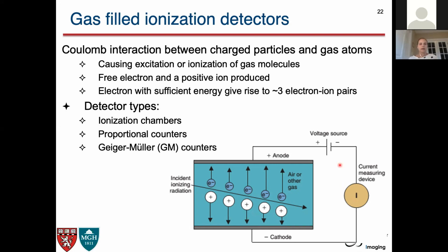Depending on the size of the voltage that we apply here, gas-filled detectors will behave in different ways. And it's common to talk about three different types: ionization chambers, proportional counters, and Geiger-Müller counters.